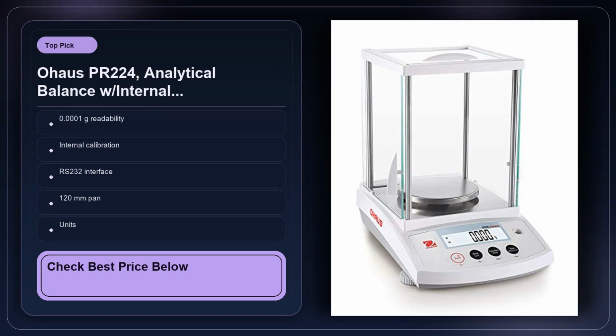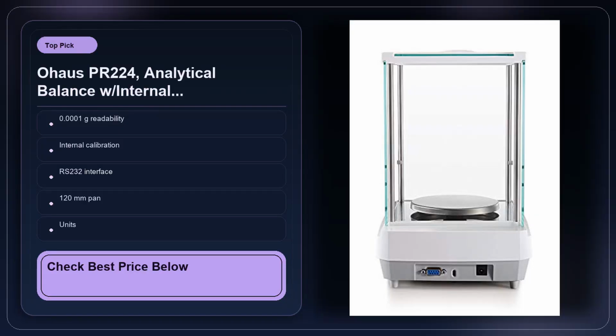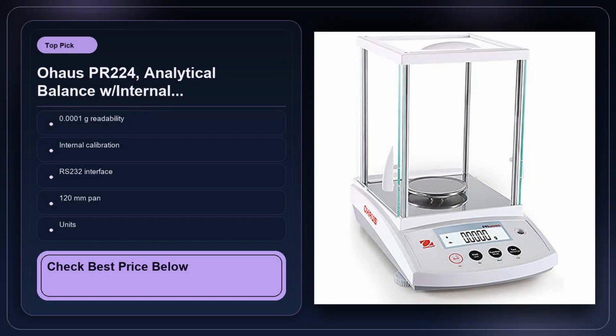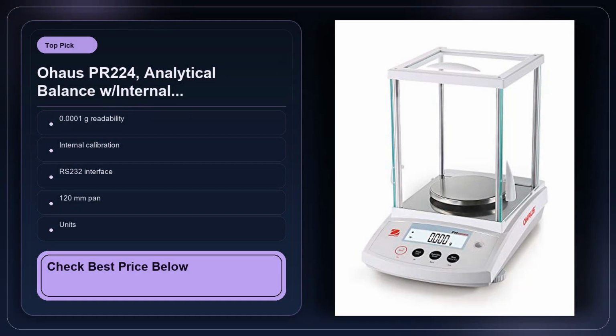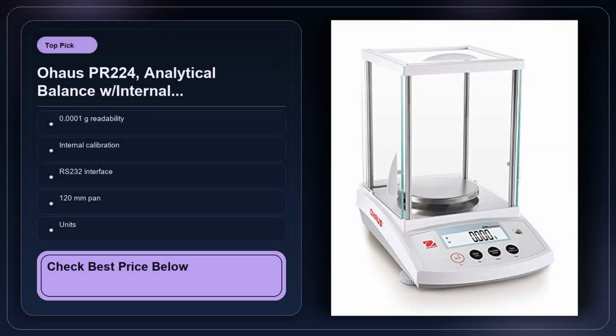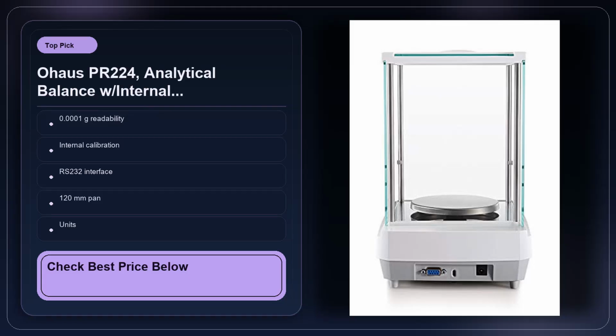Conversely, if you're working in a high-throughput pharmaceutical environment where you need to weigh up to a kilogram with sub-milligram precision, the PR224 will feel cramped. The limited pan size, the reduced resolution near capacity, and the lack of advanced features like automatic data logging or connectivity to lab information systems make it a less optimal choice for those settings. Also, if you're a forensic analyst who needs to meet strict accreditation standards, you'll likely need a balance that offers built-in documentation and audit trails, which the PR224 does not provide.